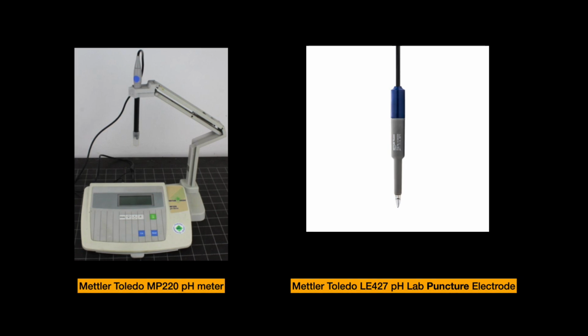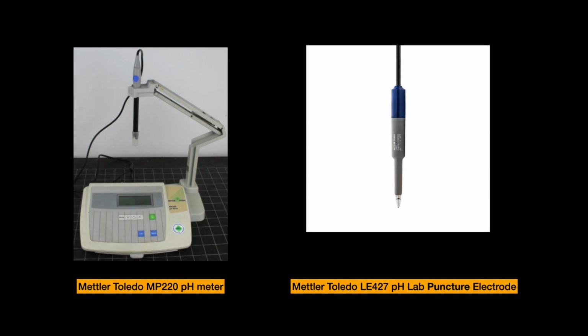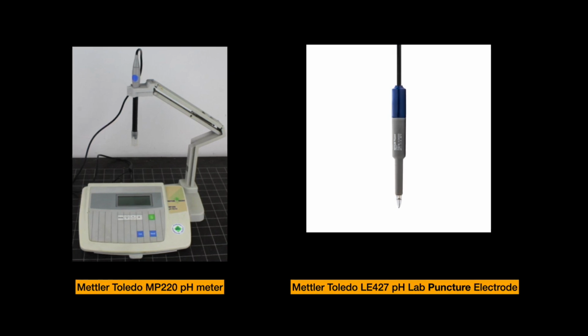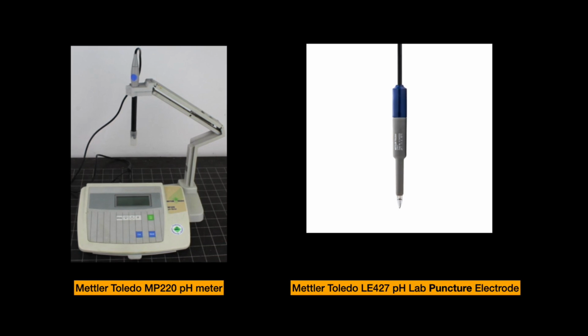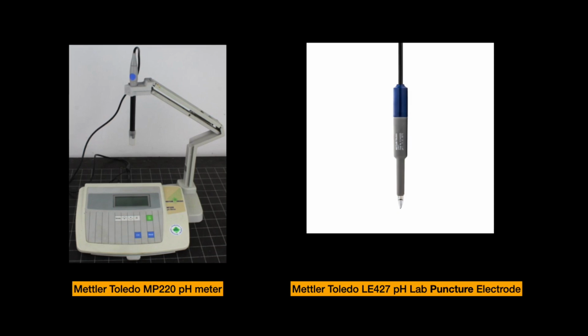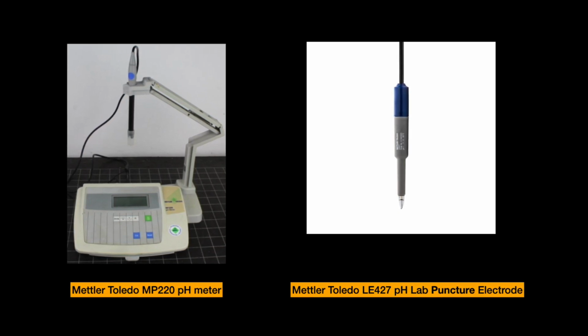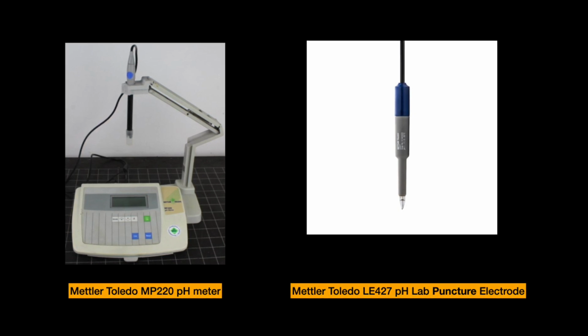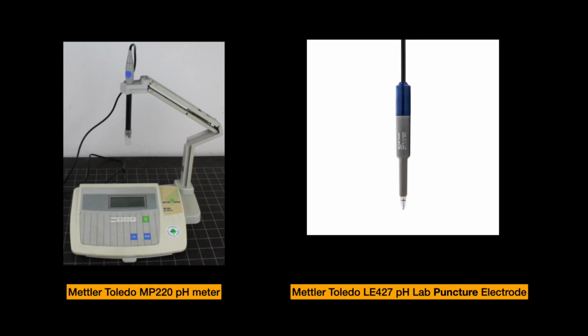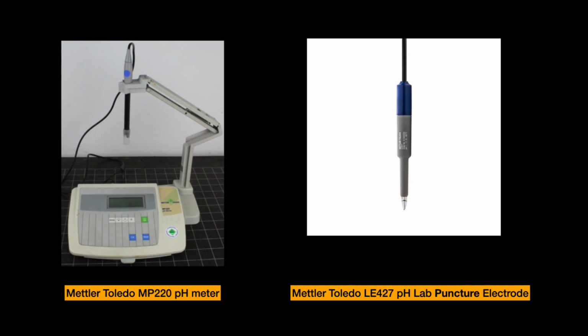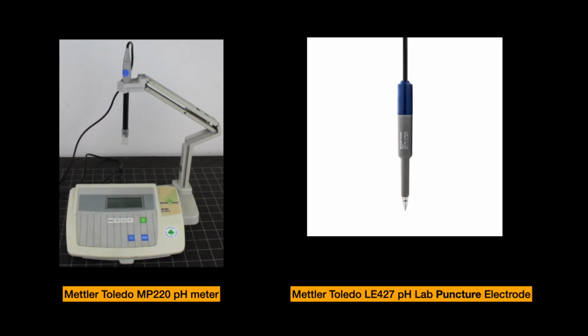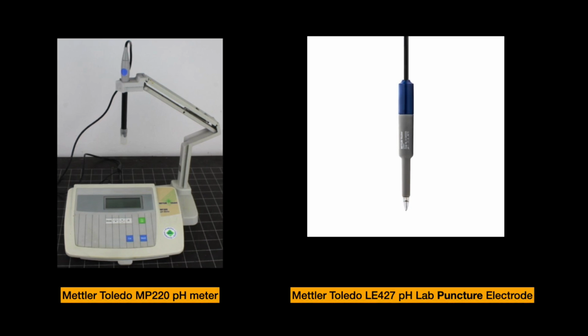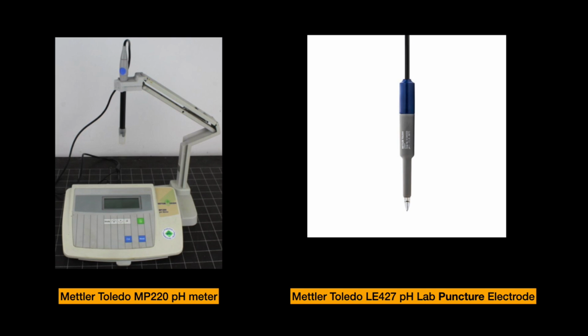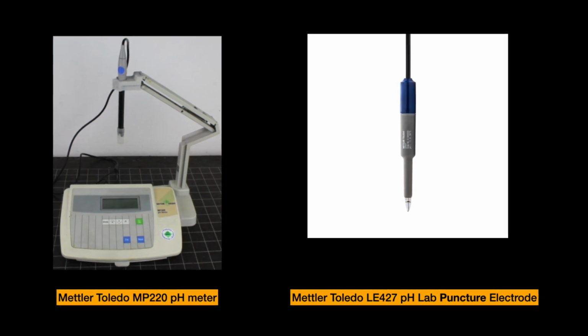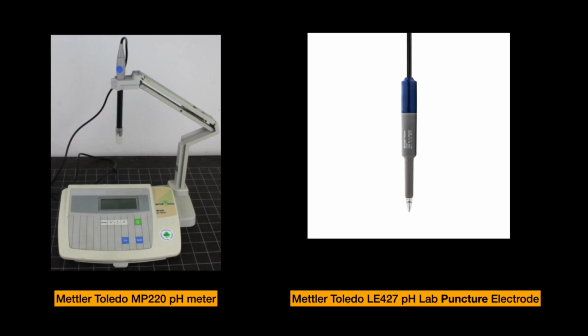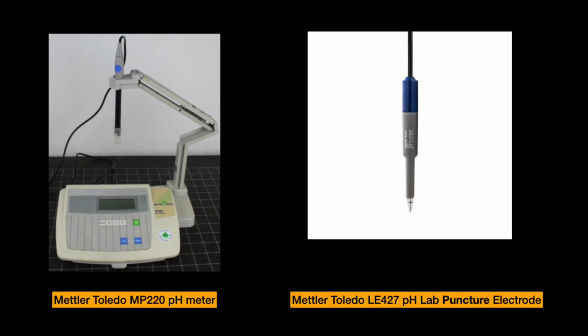But of course, you cannot use the standard electrode that comes with it to measure pH of food, because you would not get accurate measurements and you would damage the electrode. This is because a standard electrode has a porous junction that allows the reference electrolyte to slowly seep out and make electrical contact with the sample. Food samples are of course full of proteins and fats. These can clog the porous junction. A clogged junction would lead to slow and unstable readings, and eventually the electrode would become unusable. Do not use standard electrode to measure pH of food samples.